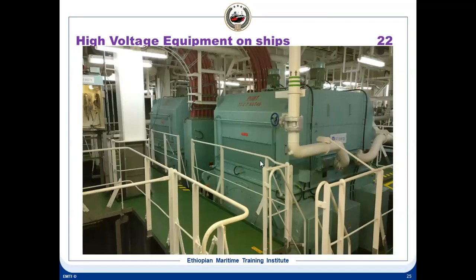Okay, this is the propulsion motor. This is also a high voltage motor, number 2 propulsion motor. So there are 2 propulsion motors, 2 shafts. You can see this cable here. I want to show you this cable color. You see, these are the high voltage cables. The cable color looks pink. It's not black. The high voltage cables are pink cables and they are separately routed. It is totally separate from the other wirings.